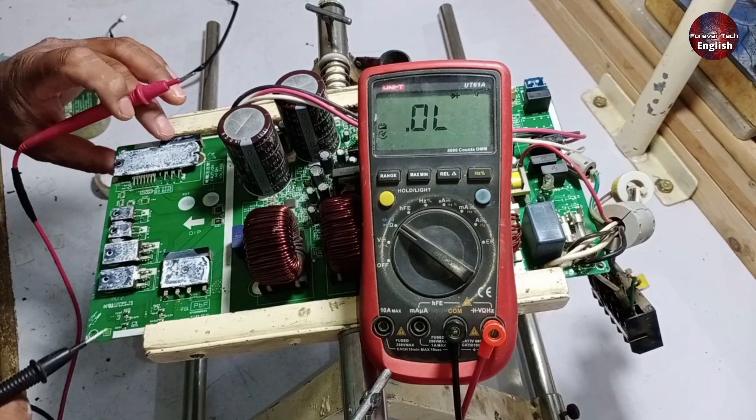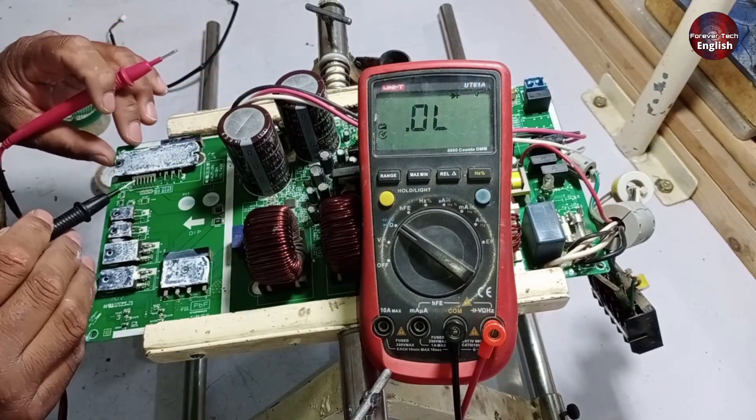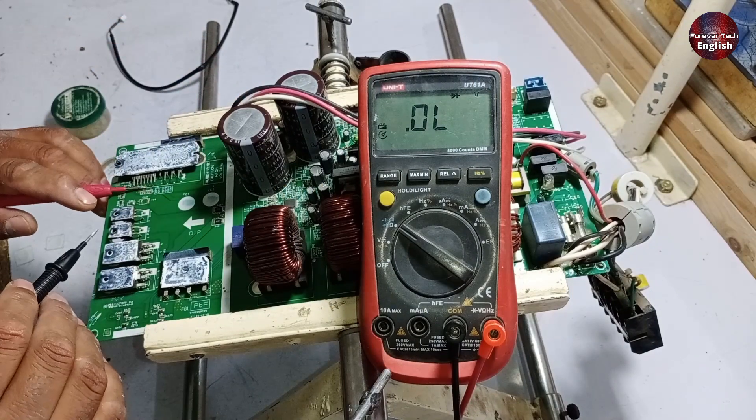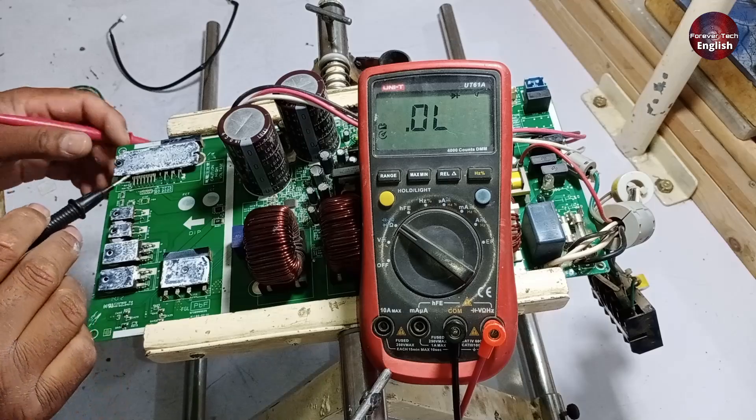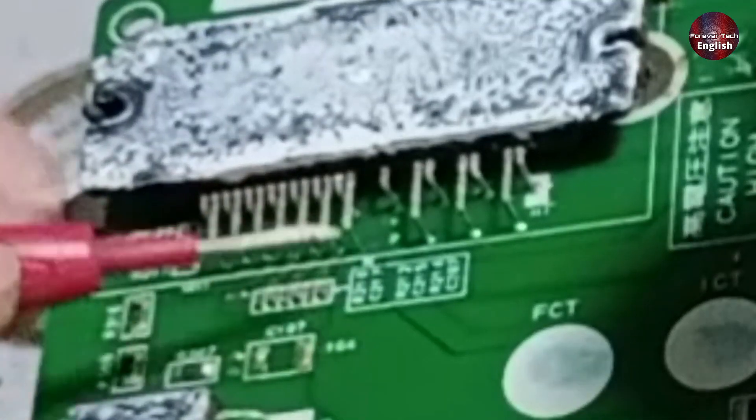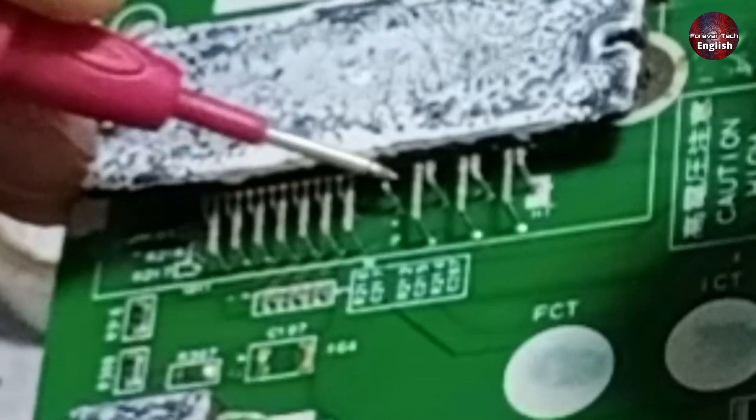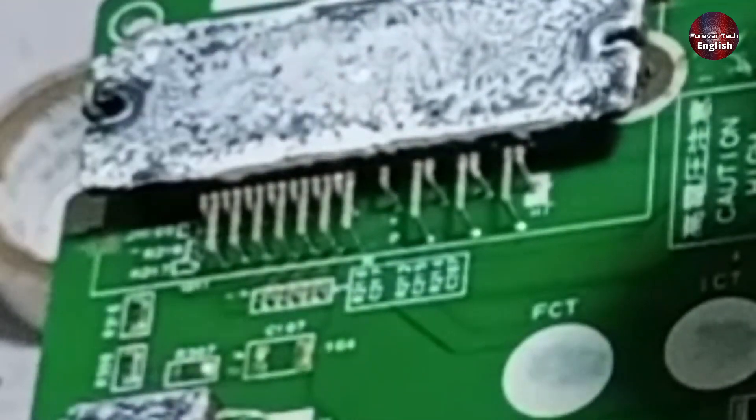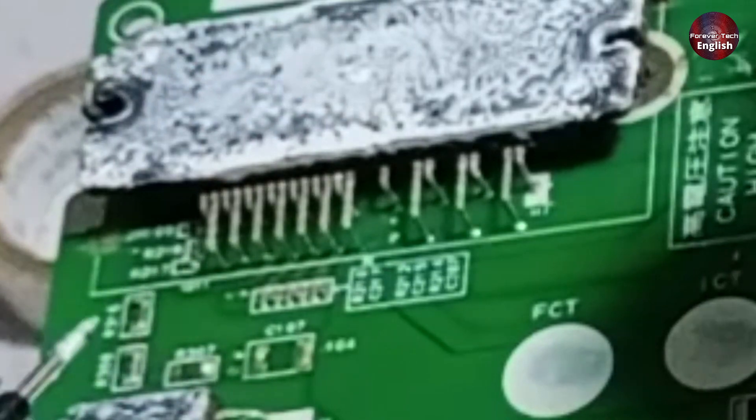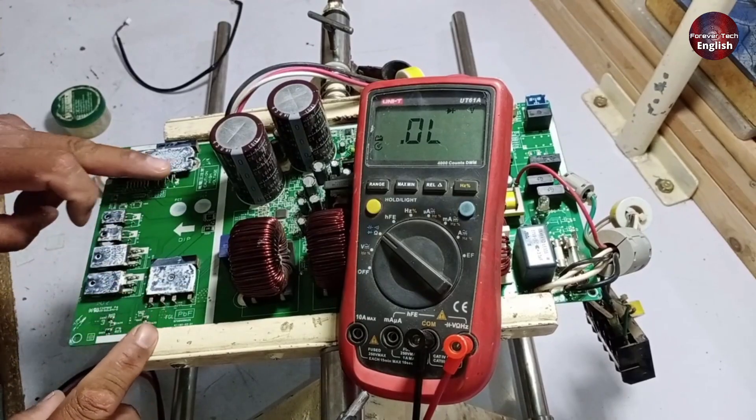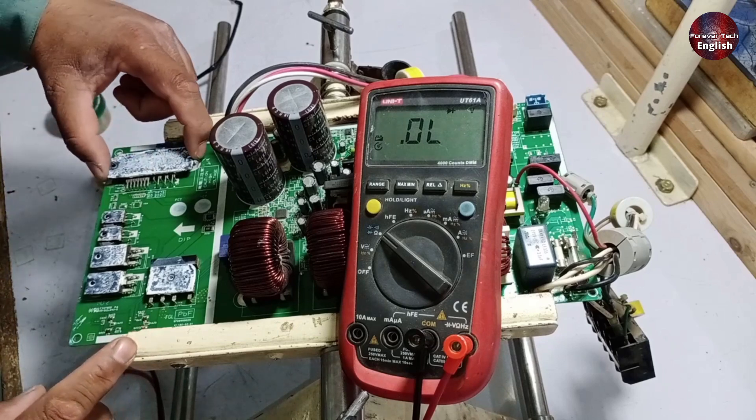Now let's check the IPM. This one is slightly different. To test a different IPM, you need to have its datasheet and know the pin configuration. Looking at this, we can see that this pin is neutral, and the inner pin is positive. After that, we have U, V, and W, so you need to test this IPM with the same procedure I told you about in another video. We have checked all the high side connections, and we have also checked the IPM.